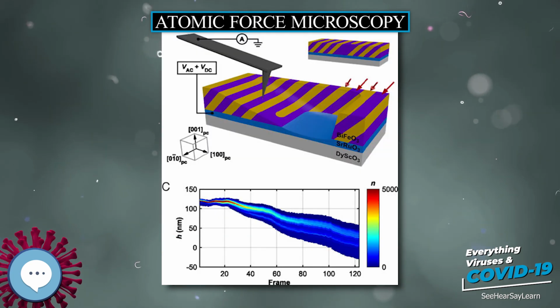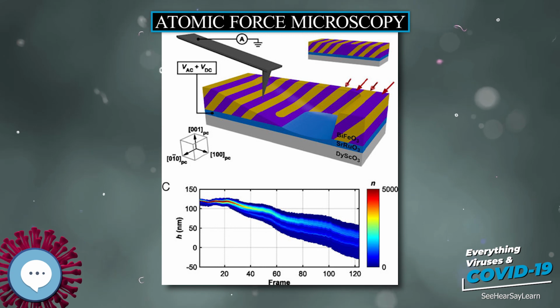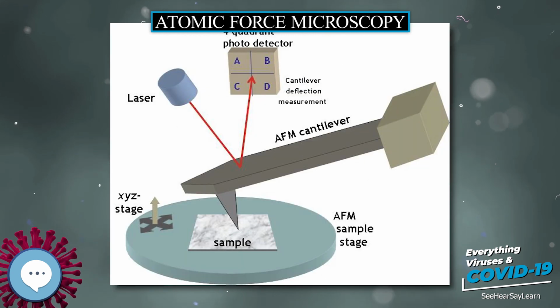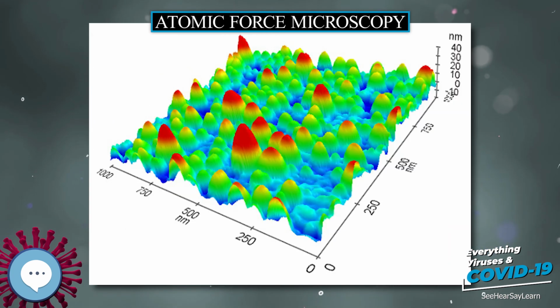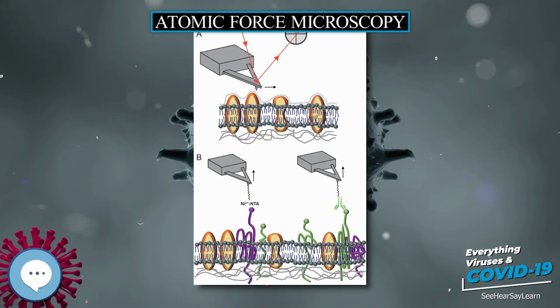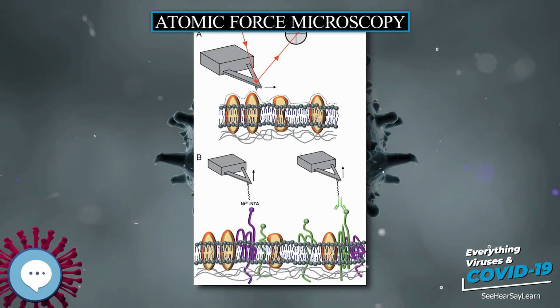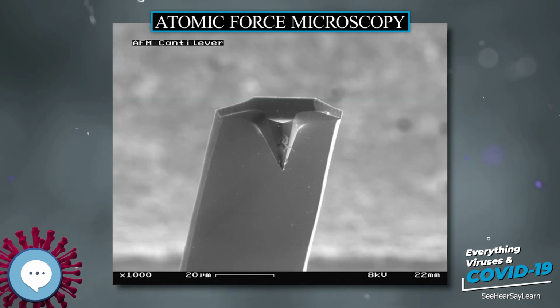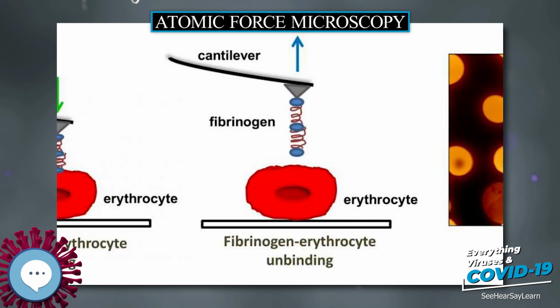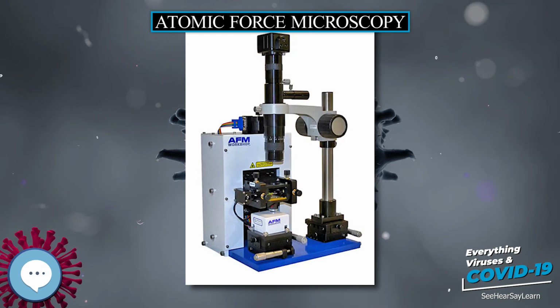Tapping mode. In ambient conditions, most samples develop a liquid meniscus layer. Because of this, keeping the probe tip close enough to the sample for short-range forces to become detectable while preventing the tip from sticking to the surface presents a major problem for contact mode in ambient conditions. Dynamic contact mode, also called intermittent contact, AC mode or tapping mode, was developed to bypass this problem. Nowadays, tapping mode is the most frequently used AFM mode when operating in ambient conditions or in liquids.